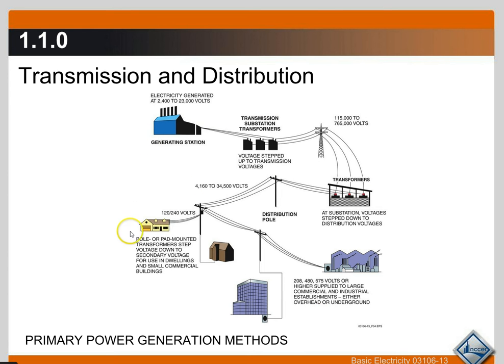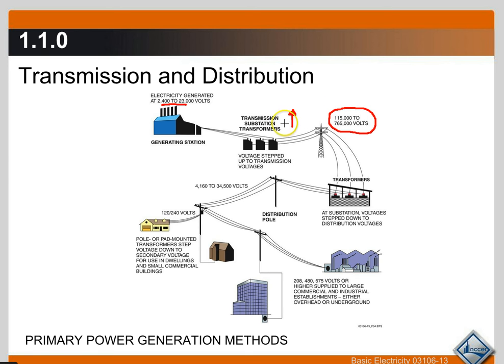The primary generators have those windings turning inside the magnetic lines of force. Output starts between 2,400 and 23,000 volts, and it goes to a substation very near the generating station. It passes through transformers which step the voltage up to a higher voltage — up to 100,000 to nearly a million volts, depending on the design and length of the transmission wires — so that the electrical power can be transmitted through miles and miles of wire.